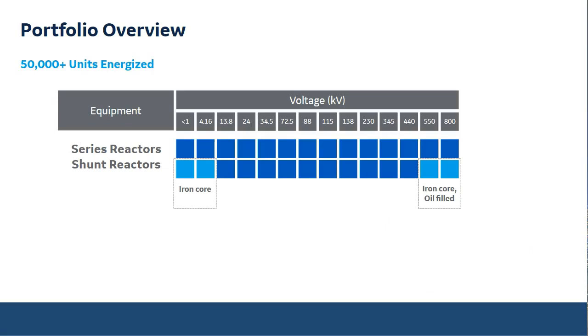Different from a circuit breaker or instrument transformer, reactors are not divided by voltage levels like a CT or a breaker would be. We created here two families. One is called series reactors, and another family is called shunt reactors. As the name says, series reactors are series connected to the line. The main characteristic of a series reactor is the voltage that's applied between the two terminals of the equipment. The voltage is basically the current that flows through that reactor multiplied by the impedance, what we call voltage drop. Compared to a shunt reactor, this voltage is much, much lower.